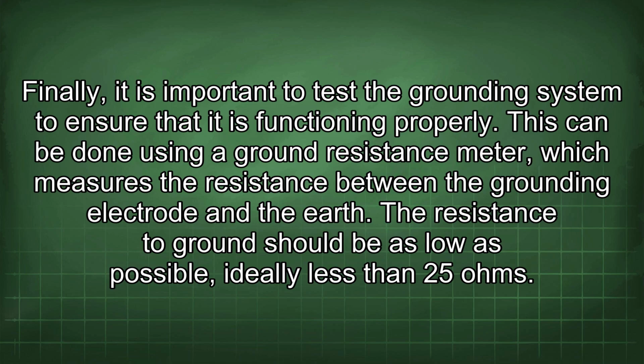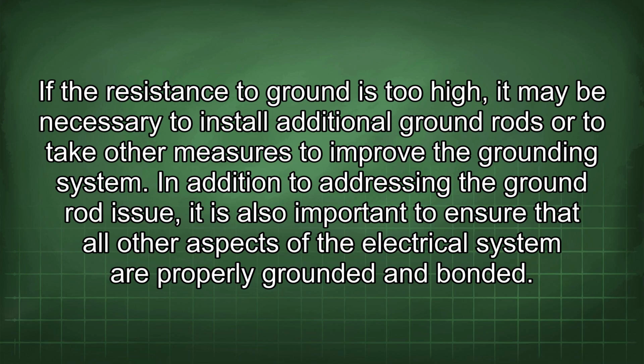This can be done using a ground resistance meter, which measures the resistance between the grounding electrode and the earth. The resistance to ground should be as low as possible, ideally less than 25 ohms. If the resistance to ground is too high, it may be necessary to install additional ground rods or to take other measures to improve the grounding system.